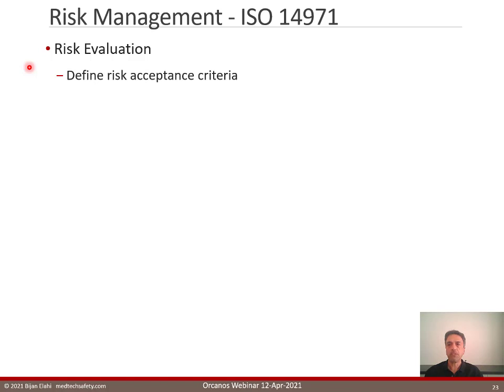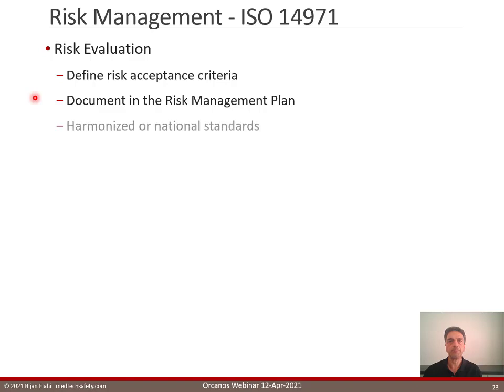To do risk evaluation, we need to have risk acceptance criteria. So we evaluate the risks by comparing our estimated risks against the risk acceptance criteria. The risk acceptance criteria must be documented in our risk management plan. So we have done this already, but at this point, we can find it in the risk management plan. Sometimes we can find harmonized or national standards that address some of our hazards. That's a fortunate thing. We can use conformity to those standards as risk acceptance criteria. But many times there aren't any standards related to a hazard that we are trying to control.